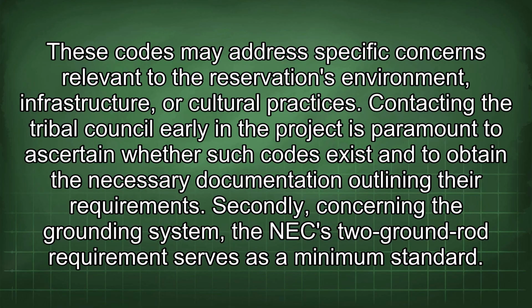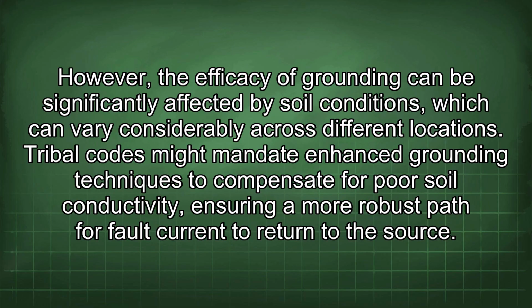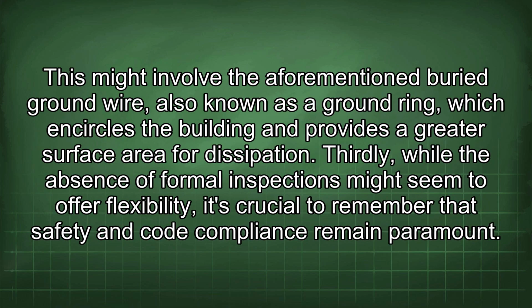Secondly, concerning the grounding system, the NEC 2 ground rod requirement serves as a minimum standard. However, the efficacy of grounding can be significantly affected by soil conditions, which can vary considerably across different locations. Tribal codes might mandate enhanced grounding techniques to compensate for poor soil conductivity, ensuring a more robust path for fault current to return to the source. This might involve the aforementioned buried ground wire, also known as a ground ring, which encircles the building and provides a greater surface area for dissipation.